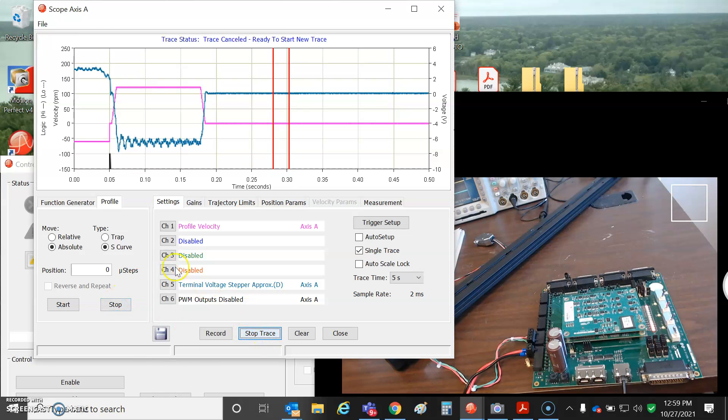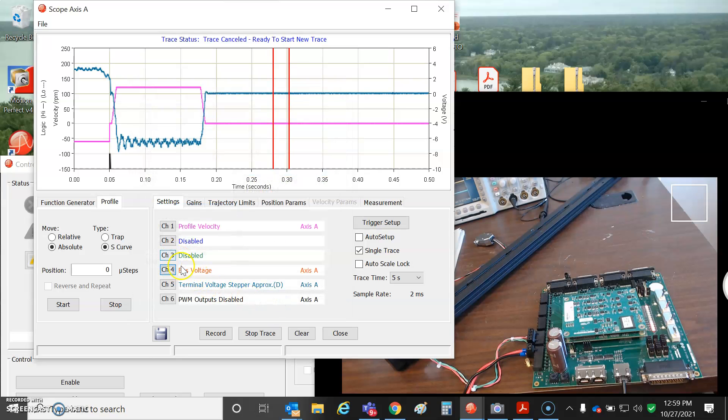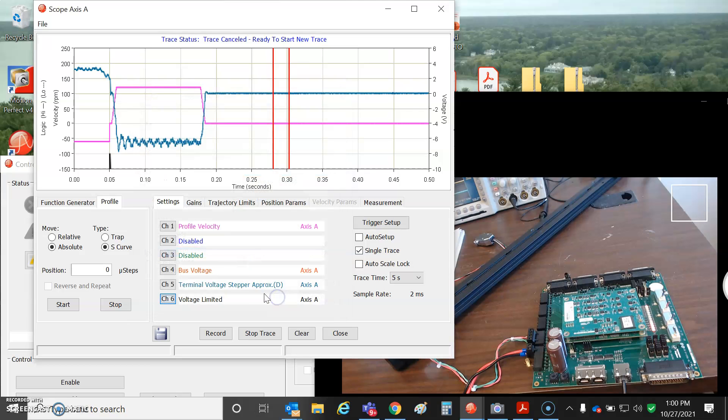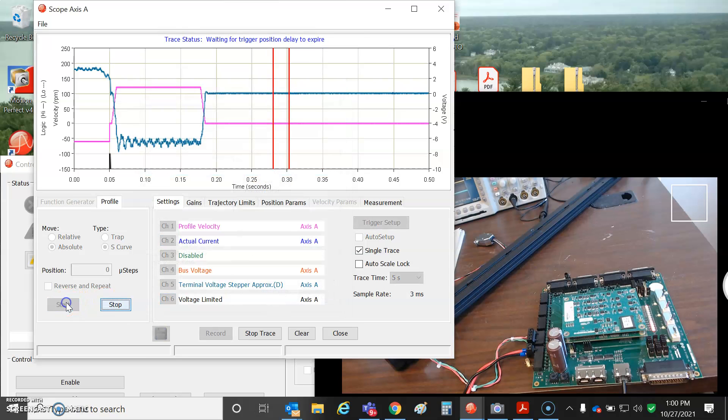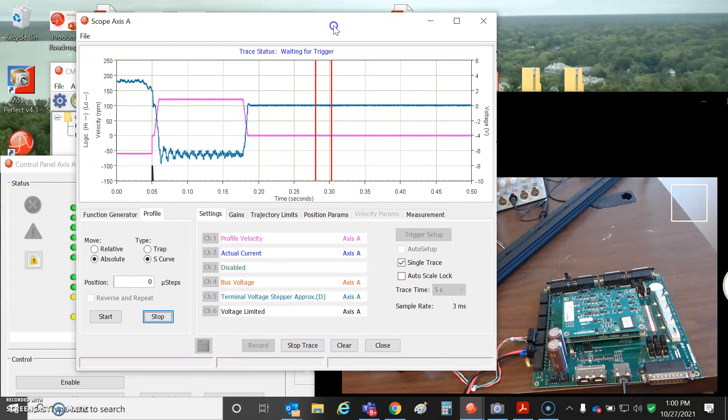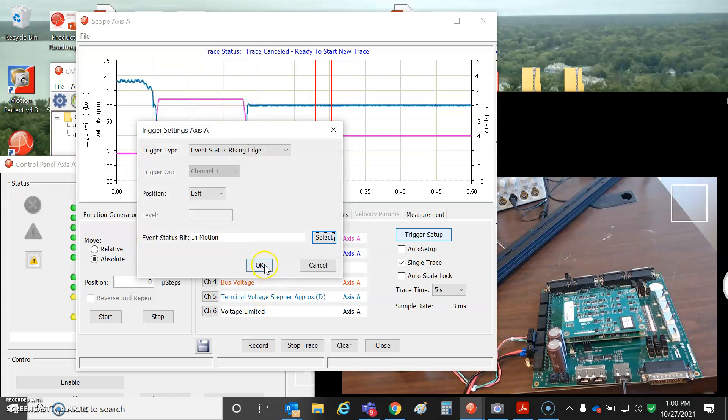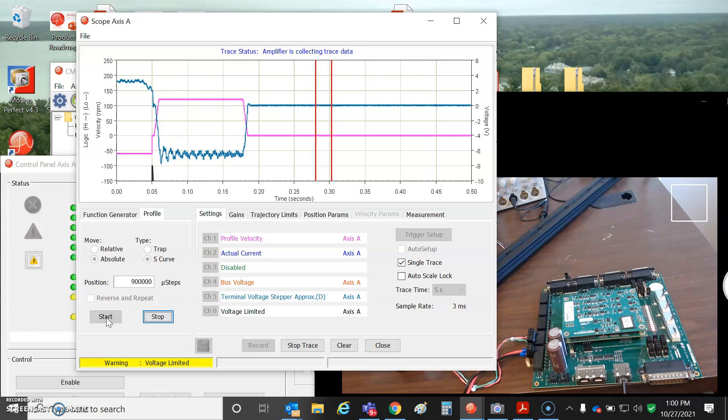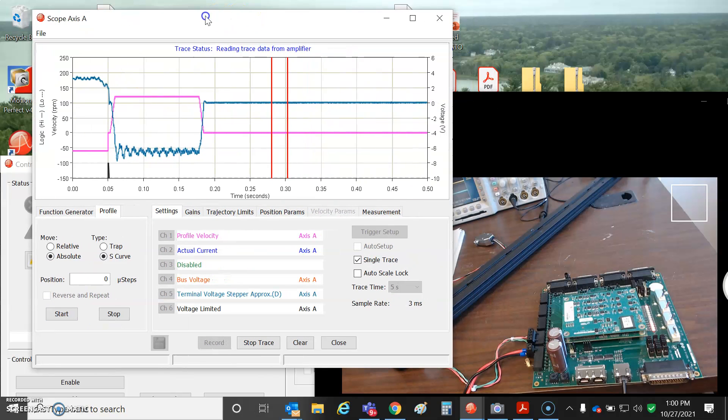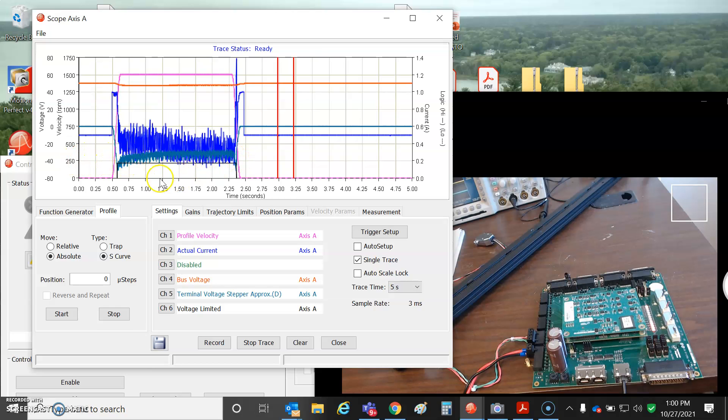Stop trace. I'm going to put in voltage bus because I'm using the voltage. And we'll do voltage, event status, warning, voltage limited. You're always voltage limited with a stepper. You got to make sure your currents don't drop down to zero, so actual current. So that's what we'll monitor. So right back to, bam, right to the zero position. No trigger, trigger setup. Select in motion. And okay. Okay, record. All right. I didn't go too far. And reading trace data. We'll see what that looks like. Yeah, so here's the voltage when you're going fast. It's around 40 volts or so.